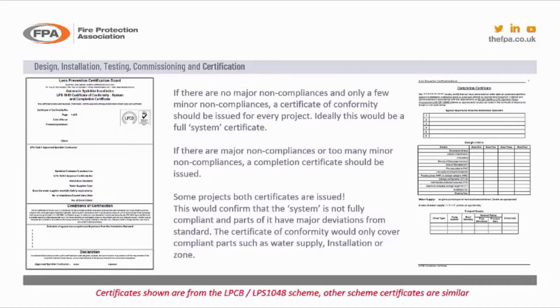However, this is not always the case. You can have some major non-compliances, unprotected areas, or a fire resistance or fire rating that doesn't comply with the standard, and it's not a permitted or necessary exception. Therefore, it could be classed as a major non-compliance. That major non-compliance will not allow a contractor to issue a certificate of conformity for the system, and on that basis, on the right hand side you can see there's a completion certificate, and that will be issued on that particular part of the system, or for the system, saying that there are major non-compliances. But again, these non-compliances should always be agreed by the authorities having jurisdiction and the insurer, which is when they are involved early doors in the writing of the correct specification.